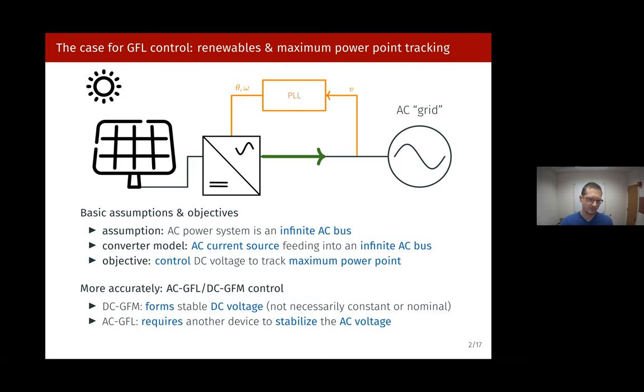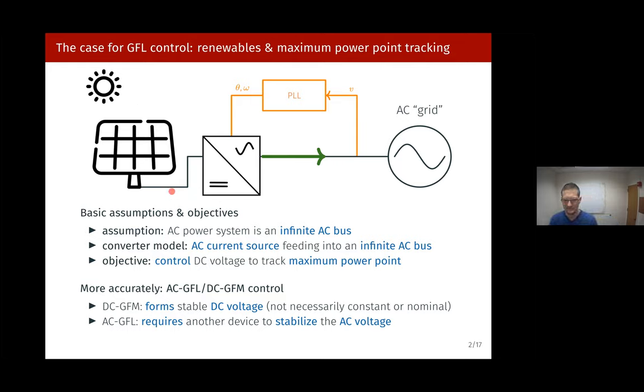For the purpose of this talk, I'll call these controls AC grid following but DC grid forming, because what they actually do is require a stiff and stable AC system to lock onto — relying on external devices to stabilize the AC terminal — and then feeding whatever power is needed to stabilize the DC side to track the maximum power point. It's not only that you're not supporting the grid; you're actively relying on the grid to create the power flow you want on the DC side.